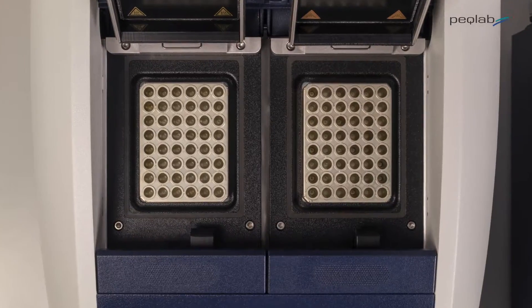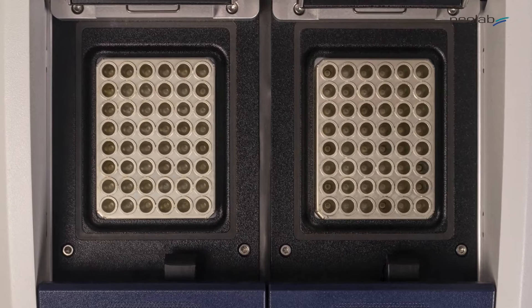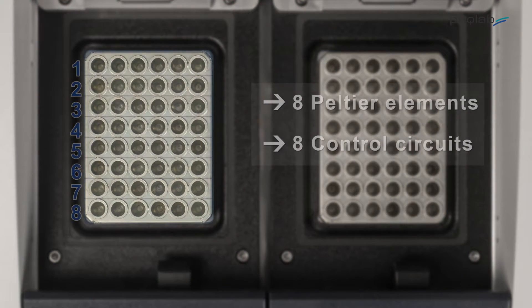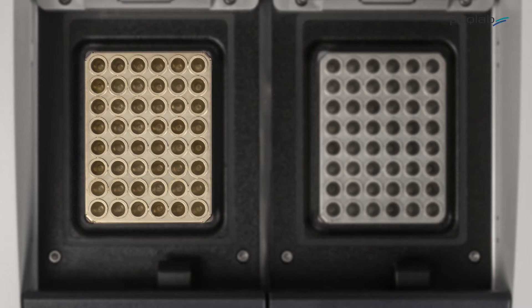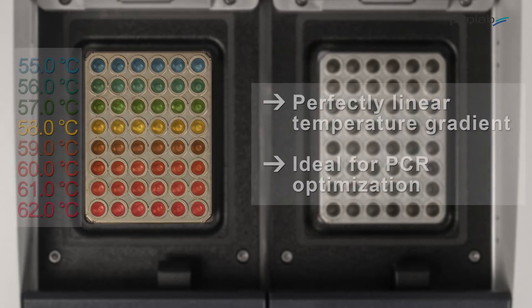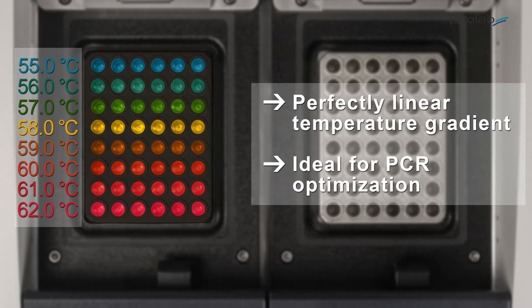Here at PEQLAB we listen closely to our customers, and we are delighted to announce two new features developed following customer requests. Flex gradient technology allows the temperature of each single row of the thermal block to be individually controlled. This novel design enables, for the first time, the generation of perfectly linear temperature gradients, ideal for PCR optimization.